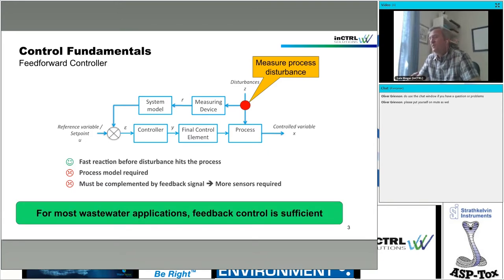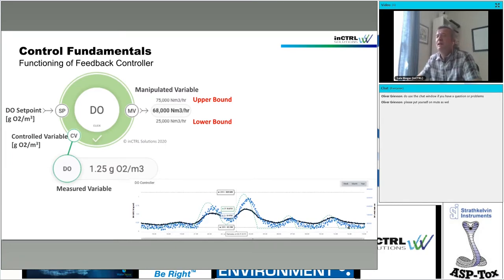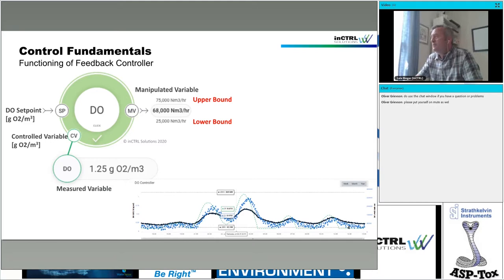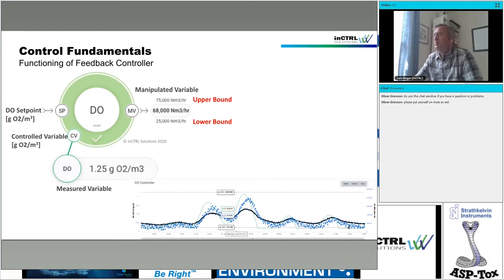In wastewater treatment, most applications feedback control would be sufficient. There are certain cases where it makes sense to go for feed forward. This is a slightly simplified visualization — the DO controller, DO set point, and control variable. Typically you calculate the difference between the two as an error and apply your control logic on it. The controller output — what the controller calculates — we call the manipulated variable, and important are the upper and lower bounds. Visualization is very, very important because operators have to understand if the system works or not and what the system is doing.